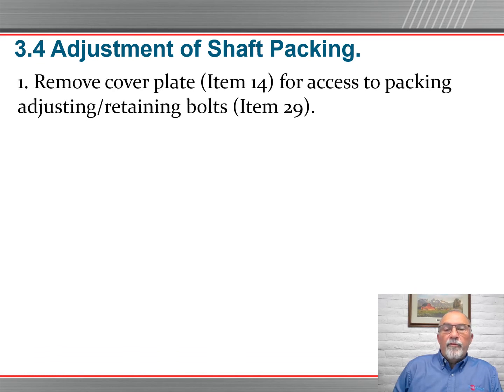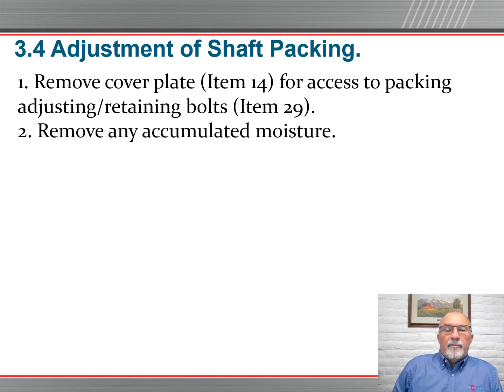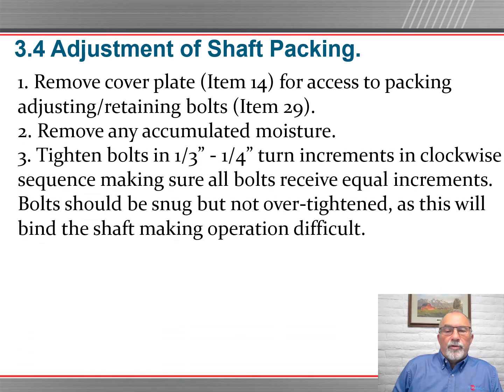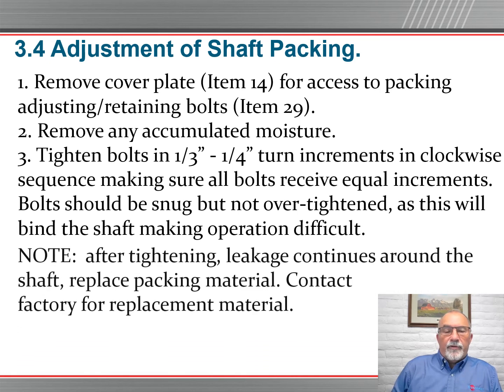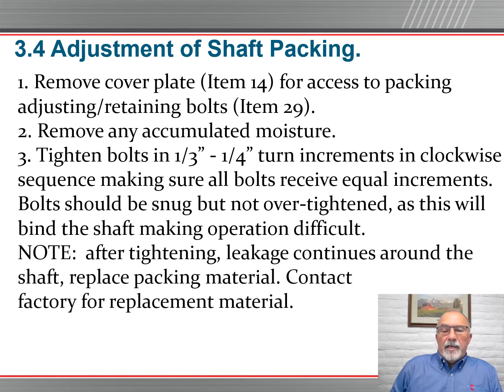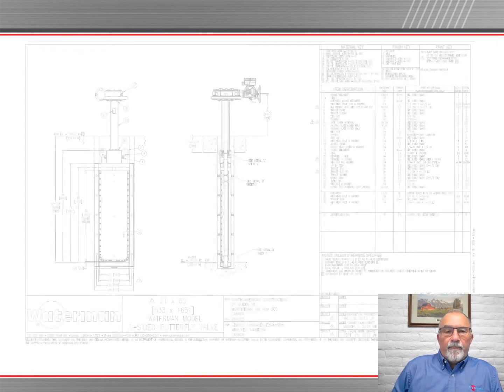Adjustment of shaft packing. Remove the cover plate, item number 14, for access to packing. Adjusting retaining bolts, item number 29. Remove any accumulated moisture. These numbers are referred to in your submittal drawings that you have on hand. Tighten the bolts in 1/3 to 1/4 turn increments in clockwise sequence, making sure all bolts receive equal increments. Bolts should be snug but not over tightened, as this will bind the shaft, making operation difficult. Note, if after tightening, leakage continues around the shaft, replace the packing material. Contact the factory for replacement material.